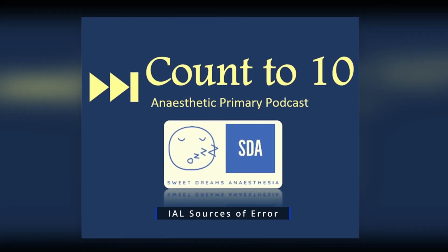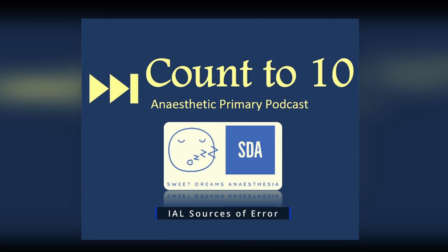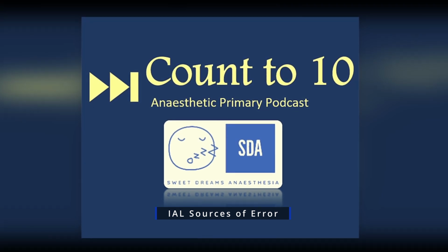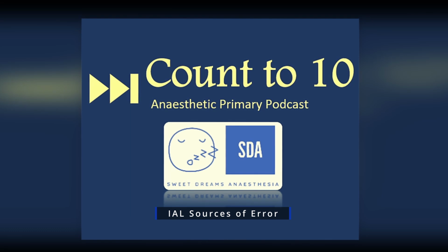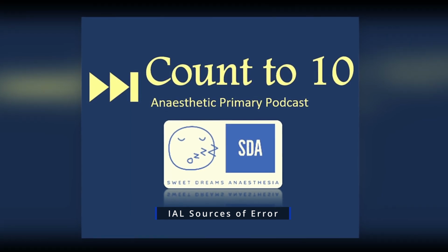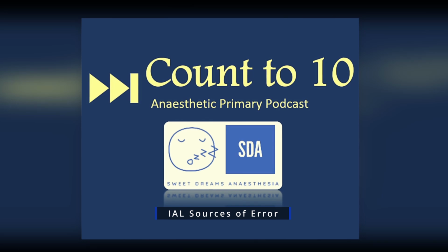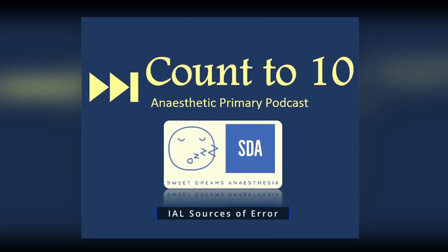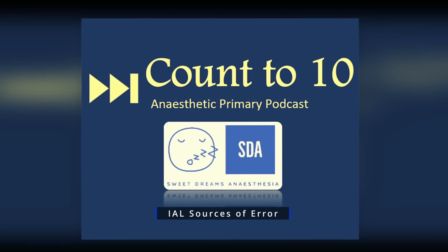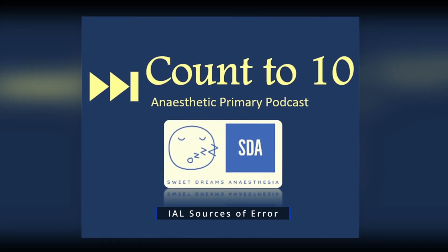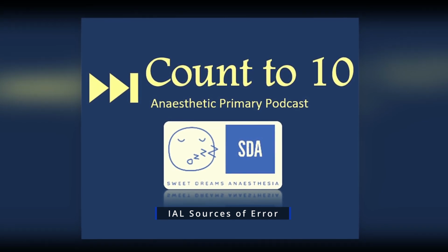The other information you can get from a fast flush test is the natural frequency of the arterial line system. The way you get this is looking at the time between the first and second oscillation after your fast flush test. This time should be less than 30 milliseconds, and 30 milliseconds corresponds with a natural frequency of at least 30 Hz. Believe it or not, I was actually asked to explain this test in my actual Viva on the day.